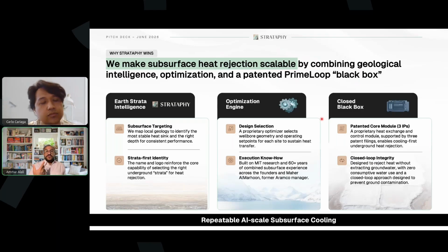These come from the normal tests you do: thermal response tests, open loop geothermal tests - which doesn't mean the system itself is open loop, but you need to flow that reservoir and re-inject it. These are very standard in geothermal heating and cooling applications. All of this gives you parameters that you run through your analysis to determine the downhole system design.